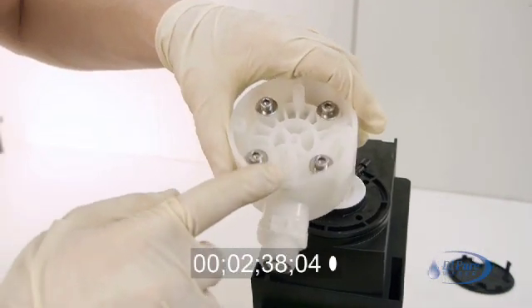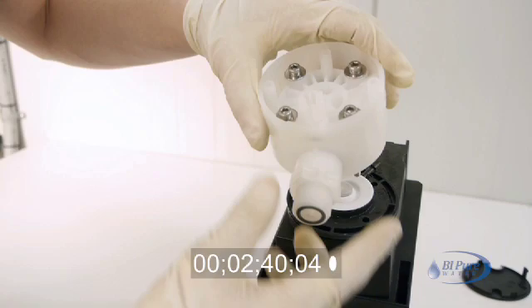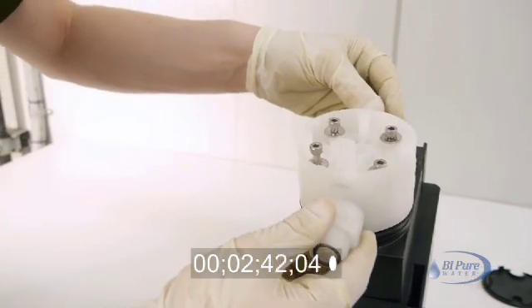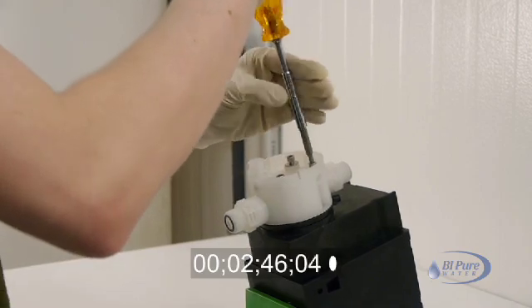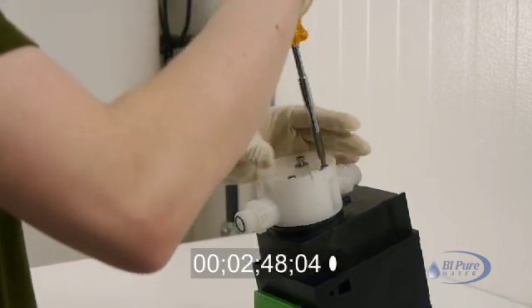With the deaeration valve pointing towards the top of the pump, reinstall the pump head. Evenly tighten the four hex bolts gradually in a star pattern as you would a car wheel.